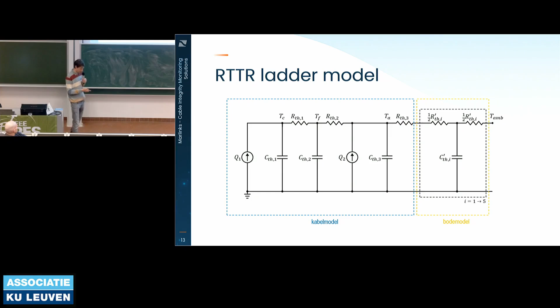If your customer asks you to use the IEC norm anyhow, you just make wrong calculations and you might overestimate, but in most cases underestimate, the effective temperature. That's not something you want during the operational phase of your cable. You just want to know the effective temperature that is there, and then we translate it and display it to our customer in a dashboard.